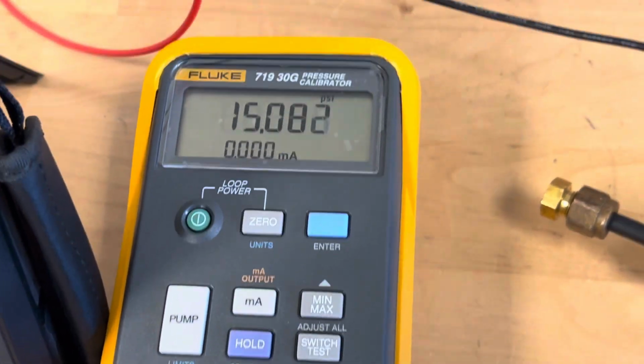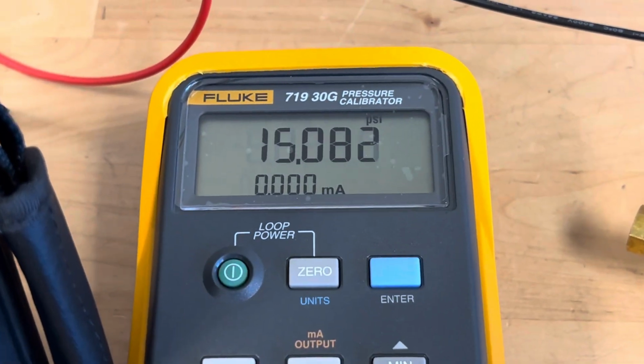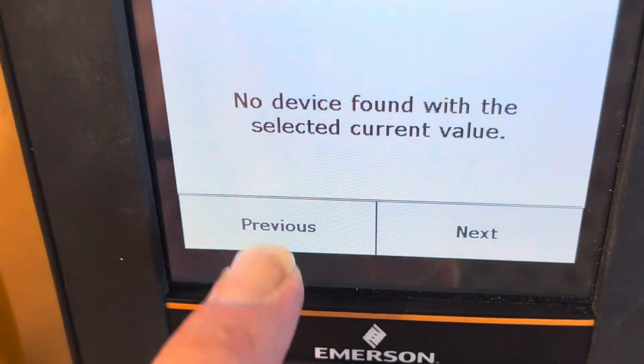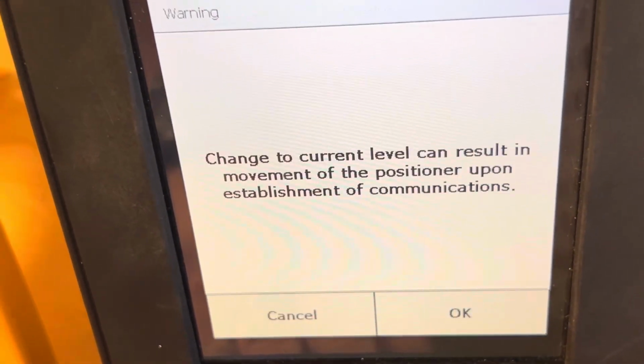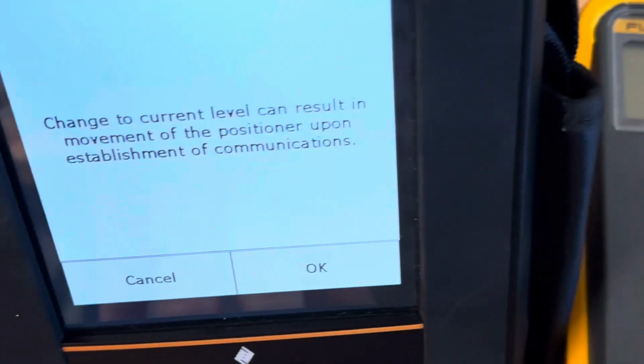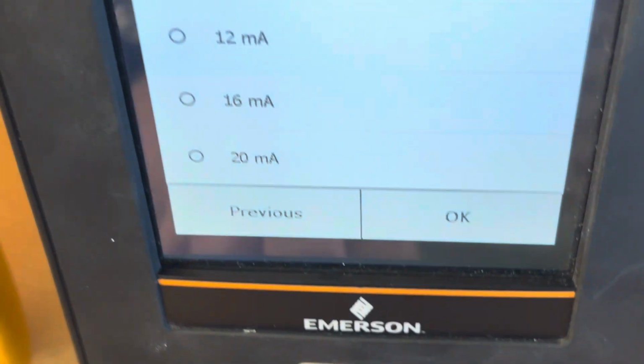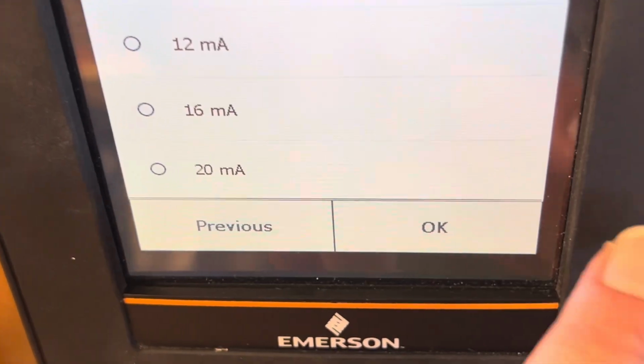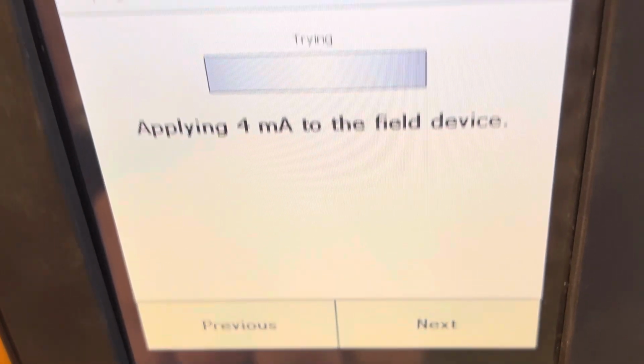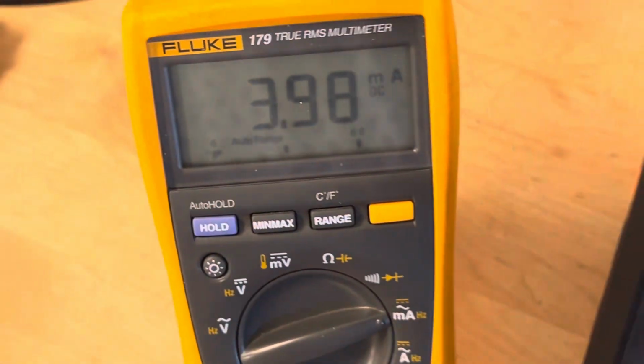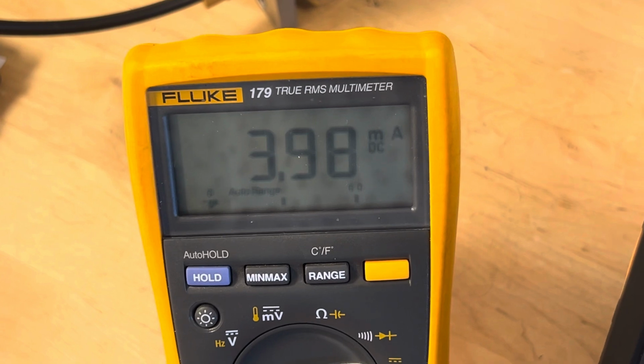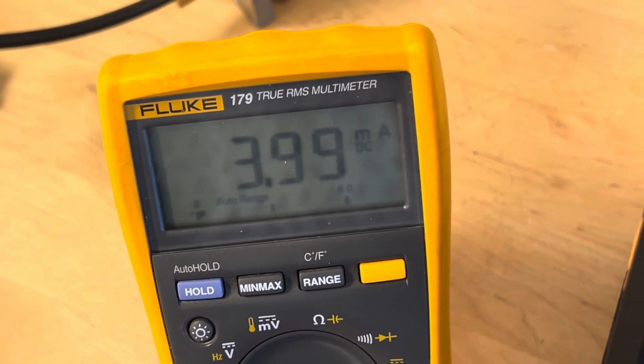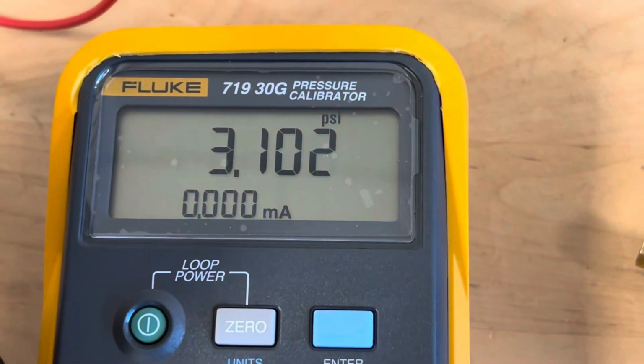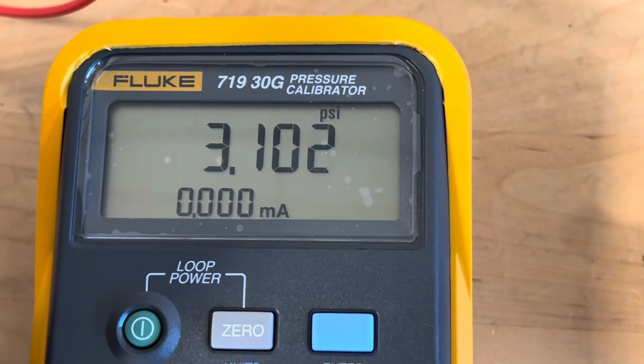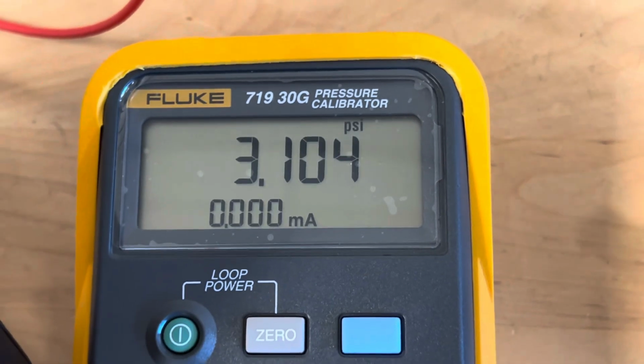Now you have to go back and forth a few times before it's totally calibrated. So let's go back to our 0. So we hit previous, and you heard the little pneumatic relay release some air pressure there. Let's hit OK. All right, now we're at our 4 again. Hit OK. It's applying 4. My Fluke 179 tells me that it's applying right at 4 milliamps. And my pressure now is 3.1. And remember a while ago we had it set to exactly 3.0.